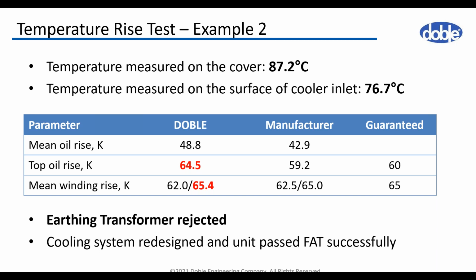we didn't accept that. So based on our calculations, we found in this case the top oil rise exceeding the guaranteed value, and also the low voltage winding rise exceeding the guaranteed value. We then rejected the transformer and insisted on improvement in the cooling system. The cooling system was redesigned, and after that we retested the unit successfully. Actually, what the manufacturer did was to install one additional radiator to improve the cooling of the transformer.